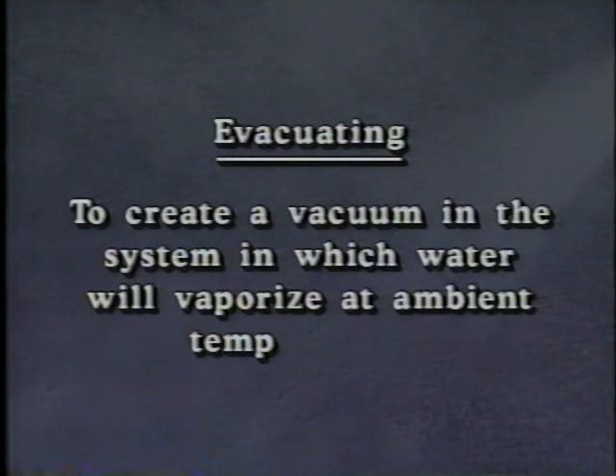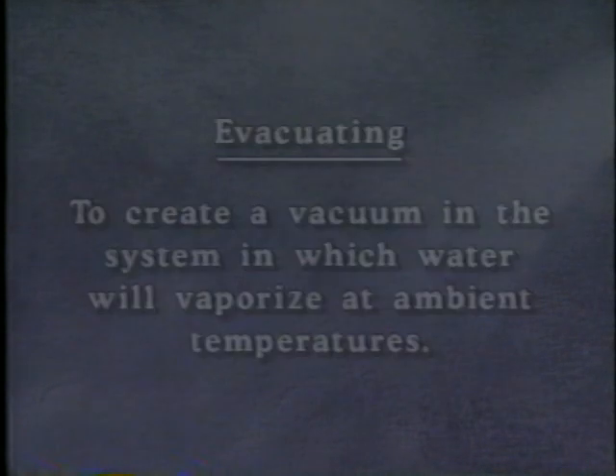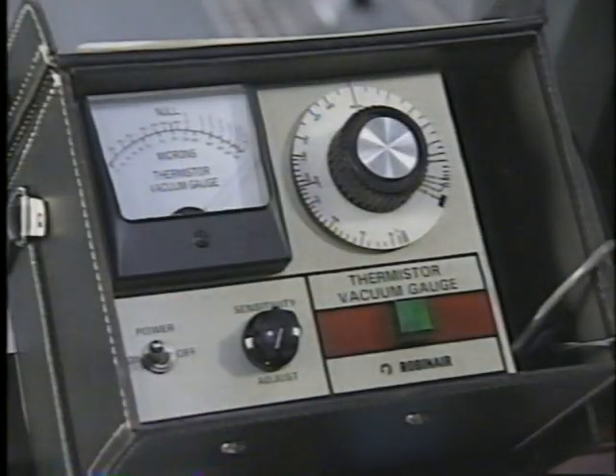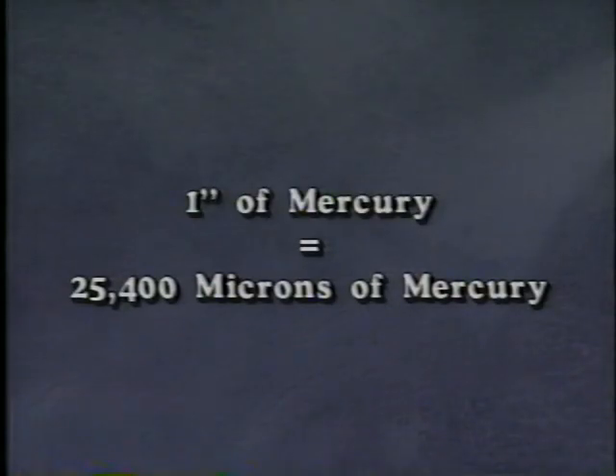Before the system is charged, it must be evacuated to remove any water vapor. This is accomplished by lowering the system pressure using a vacuum pump, causing the moisture to vaporize at ambient temperatures. Check the R134A station manual for detailed evacuation instructions. To be certain the system doesn't leak or contain any moisture, connect a thermistor gauge. This gauge measures the vacuum in the system in microns of mercury, compared to inches of mercury as indicated on the charging station's gauges. 1 inch of mercury equals 25,400 microns of mercury. Obviously a much finer and more accurate method of measurement.